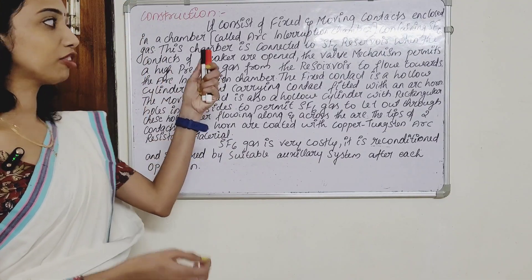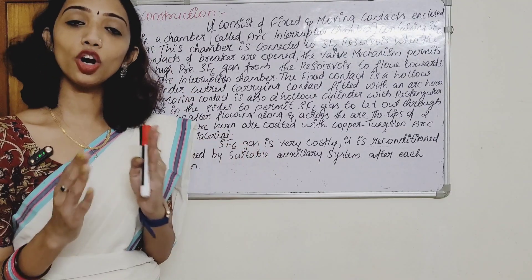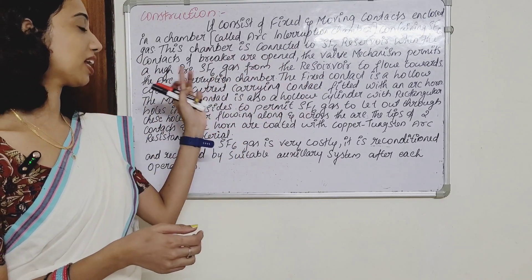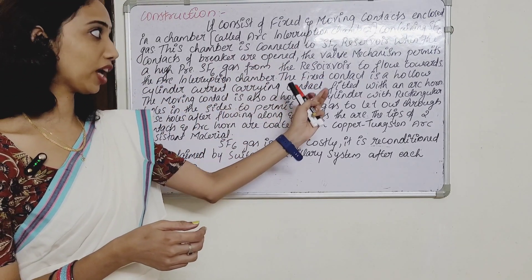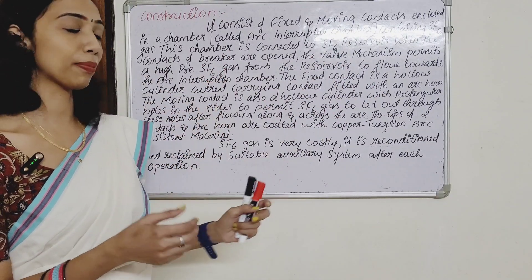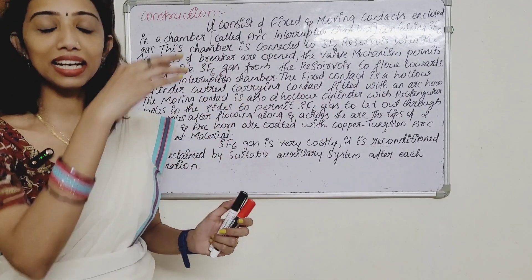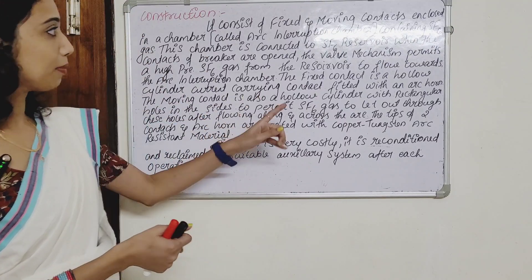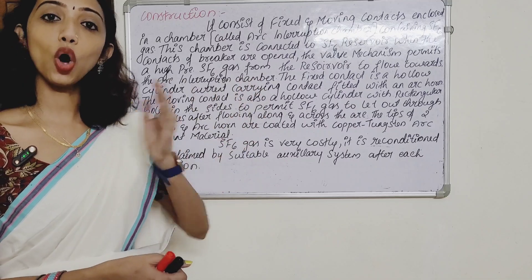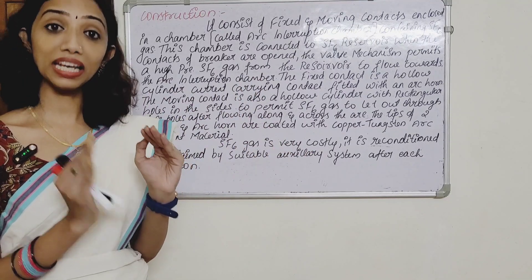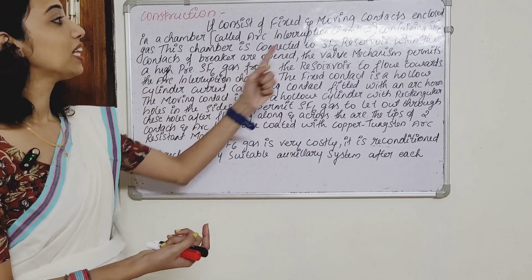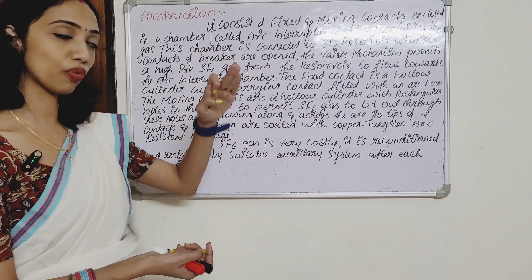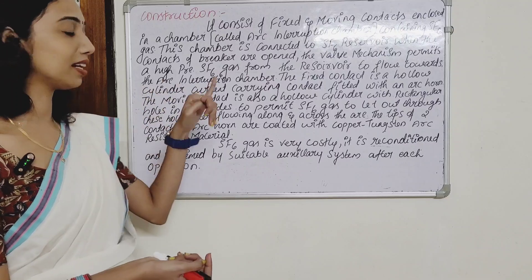When the contacts of the breaker are opened, the valve mechanism permits high-pressure SF6 gas from the reservoir to flow towards the arc interruption chamber.